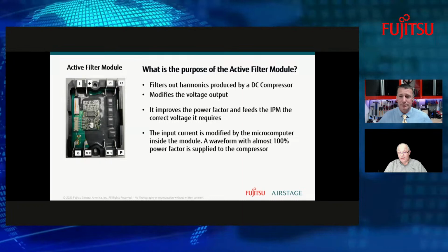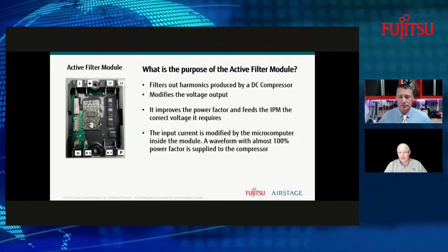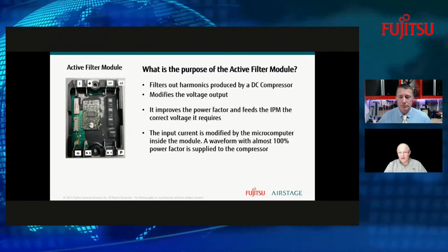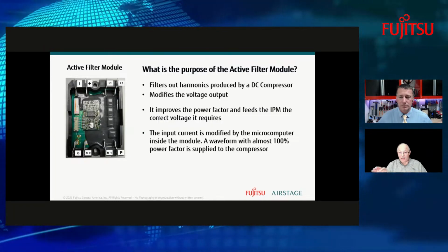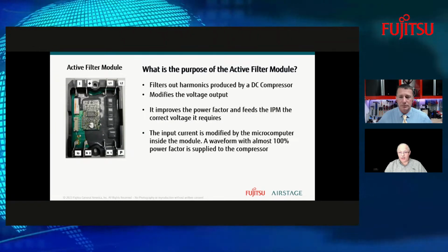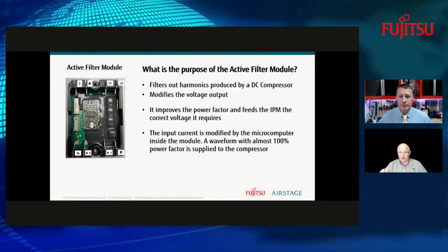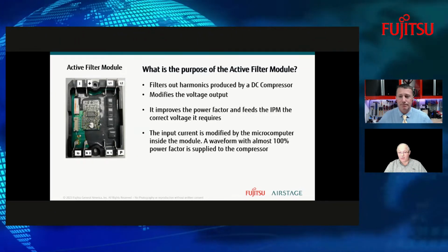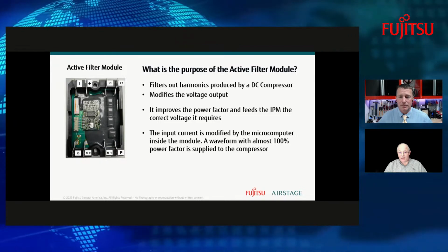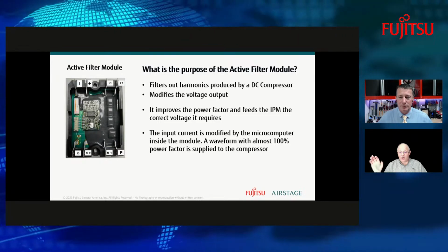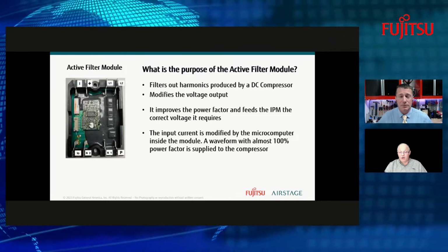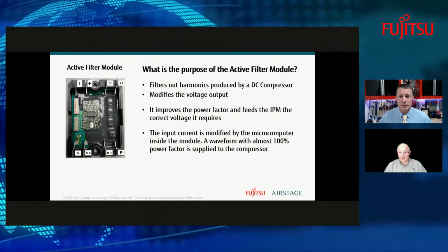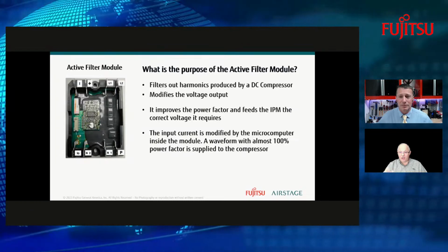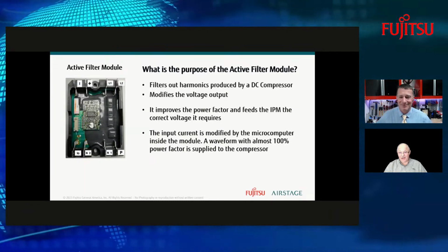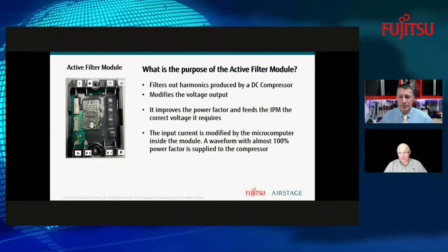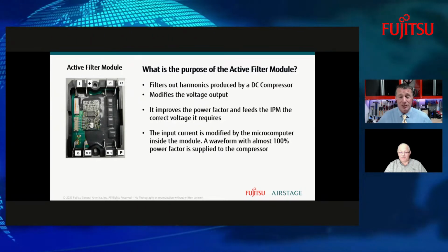Yeah, it's good insurance. And there was one who was telling us about a high school they had, and it was up on top of a big hill, and it was known for getting lightning strikes up in that area. So they put 27 of these on. Yep. Talking about it, it hit the school finally. When it did, it knocked out all the units. But when they took those off and turned the power back on, the units ran fine. It damaged those devices, yeah, absolutely, but that's what it's supposed to do, save the equipment. Yeah, that's insurance. Absolutely.